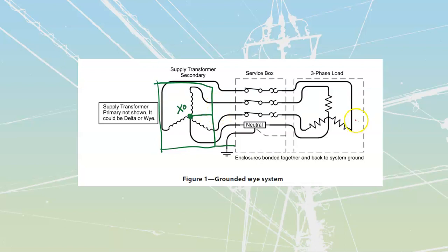Let's just take a look at that. If we had a fault on this line over here, we would send our current out along, we'd hit our grounding and bonding, and then rather than sending it all the way back up the neutral over here and then back into the transformer, that's the proper way, we could alternatively have some of it travel along here and then travel up here and hit the neutral. Now ultimately, under a fault, it's still safe because it does still hit that. But we do have two differing resistances over here in our pathway. We're going to get differing currents that split, and we're not going to have as predictable an installation.